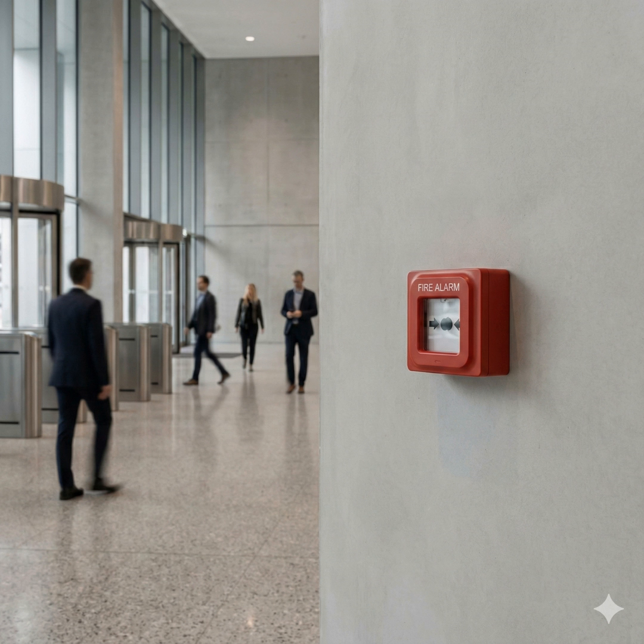Okay, now let's move to the physical elements the building occupants actually see and hear, the notification appliances. This is where the abstract code requirements of NFPA 72 directly intersect with physical safety. And the requirements here are incredibly precise. They're all evidence-based. Let's start with the audible alerts, the horns. They have to produce sound levels that exceed the average ambient noise level in a space by at least 15 dBs. That ensures it's startling, unmistakable. Right, even over normal background noise.